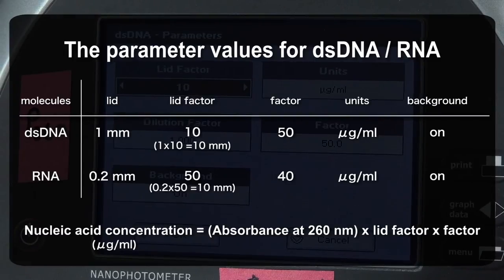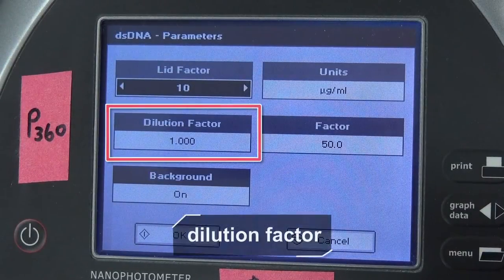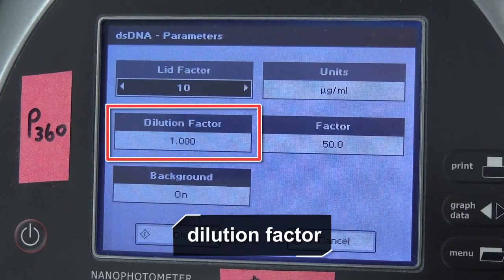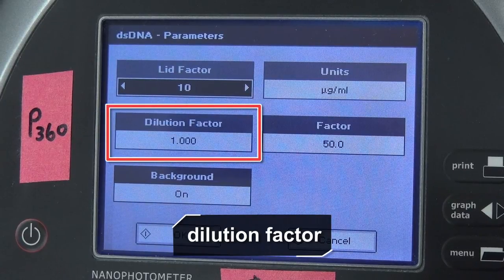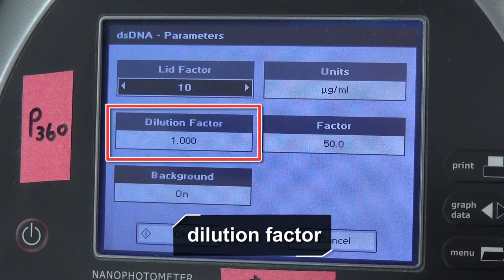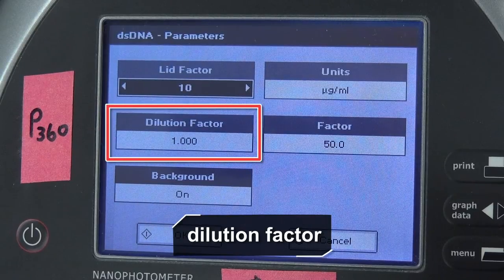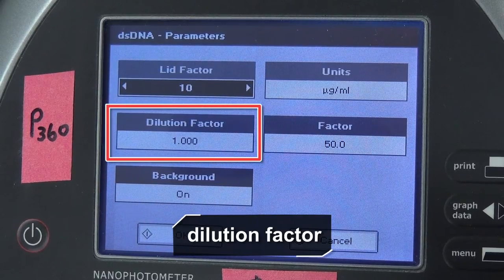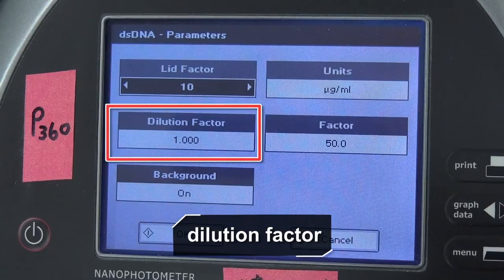Since the sample isn't diluted, the dilution factor remains as 1.000. If the sample has been diluted, you should change the factor so the spectrophotometer can convert the result into the original concentration for you.